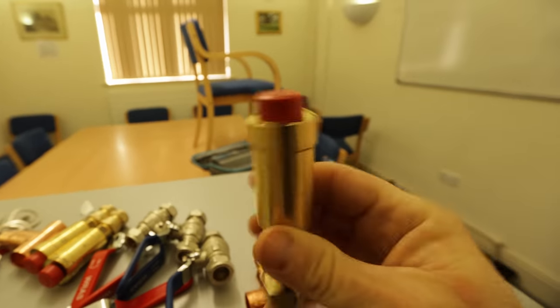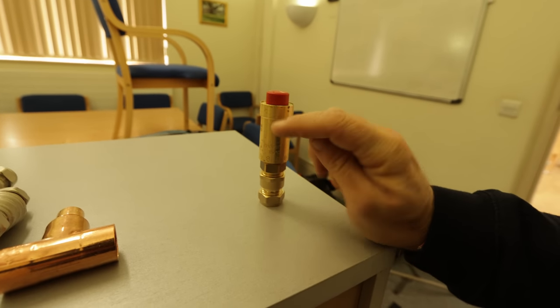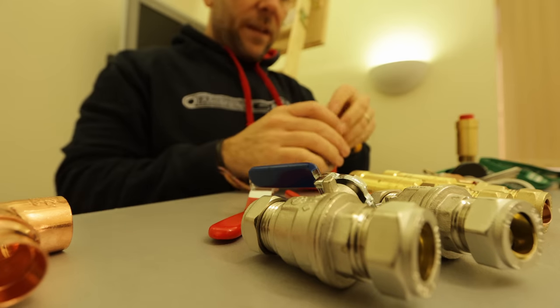So these are the air vents I'm going to fit. Automatic air vents work in a very basic way — there's a small plastic float inside with a tiny hole at the top. When full of air, the float is at the bottom, allowing air out through the hole. When it fills up with water, the float rises and shuts off, automatically closing the valve. It's good practice to install these with a little isolating valve underneath, just in case they go wrong — they are a moving part and they do fail. That way, if they go wrong, we don't have to drain the system or drop the pressure to fix it.